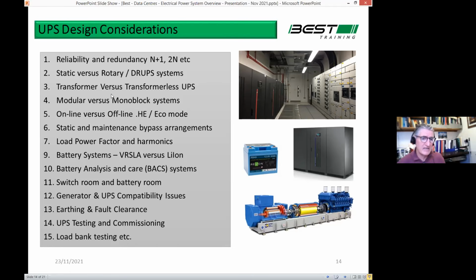So when it gets to static systems, there are lots of other considerations. There's transformer type systems versus transformer-less systems. There's modular versus monoblock, and we will show you a slide on that in a minute. How you operate it: if you operate it online, which means you're sending all your power through the rectifier and inverter, you have certain losses in the system. Most manufacturers offer what they call a high efficiency or eco mode, where you can go into bypass and just feed the load directly, without going through the inverter. Obviously, there's a risk associated with that, but the savings in a typical hyperscale data center are millions and millions of euros just in energy costs per annum by operating in eco mode. That's how important it is. And obviously there's the associated reduction in carbon emissions, so there's a lot to be looked at there.